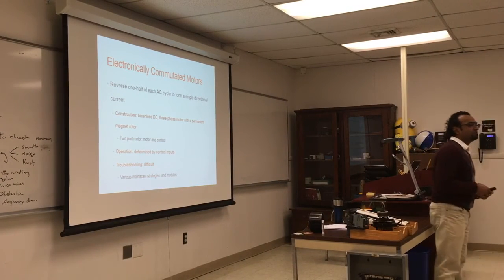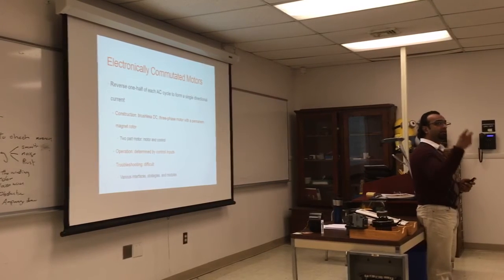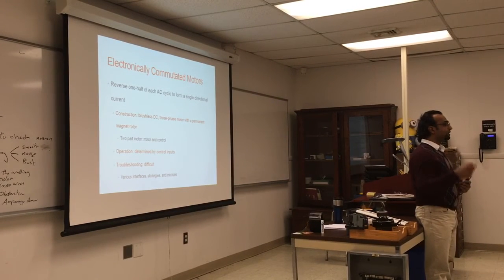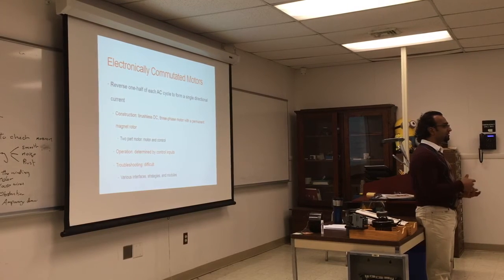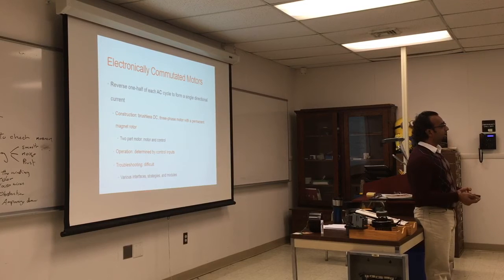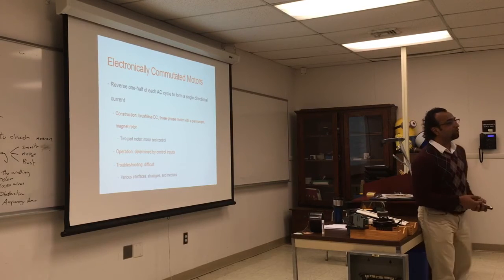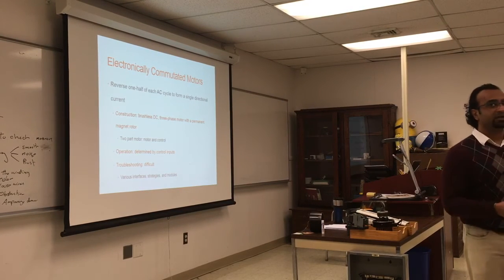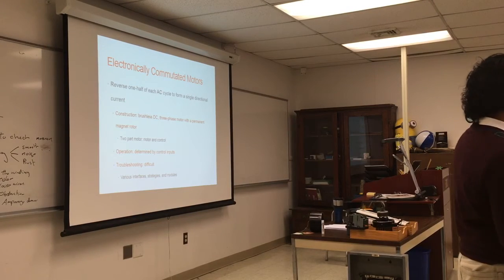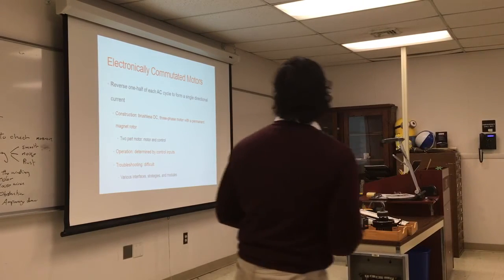Where would you find those? Sometimes in mini splits or in ACs coupled with furnaces. Why? Because you will have a high speed fan and a low speed fan, and it will modulate more. So if you go to a furnace coupled with an AC, probably you will see ECMs, electronically commutated motors.